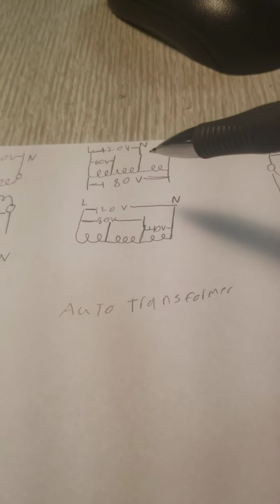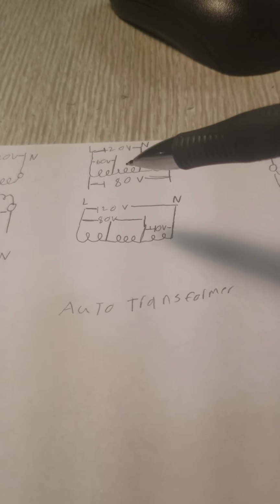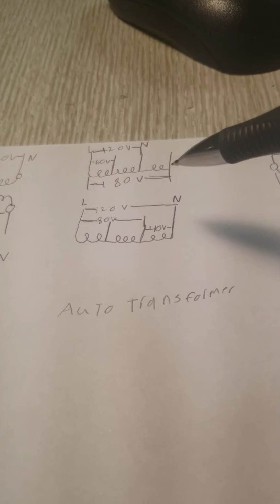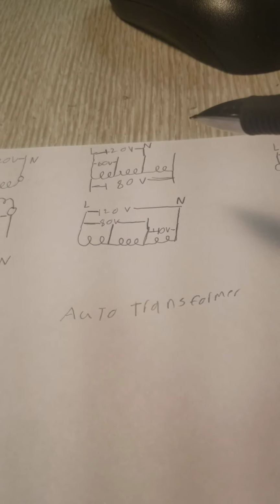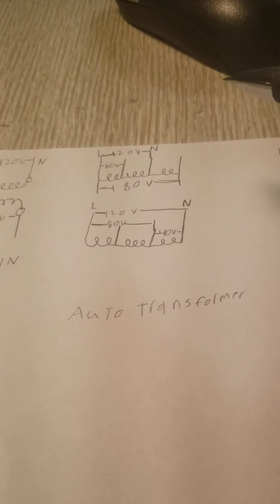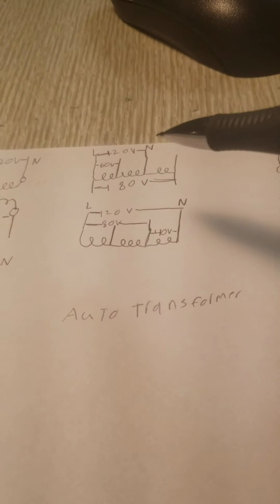So an auto transformer is a single coil wrapped around an iron core that has multiple taps. And depending on where you connect your supply and your output leads, you can get multiple different voltages out of the taps on that coil. So, for instance, in this one, if we connect 120 volts between this first lead and the third lead, we would have 60 volts between first and second lead, or between second and third. We would have 80 volts between the first and the fourth lead here.